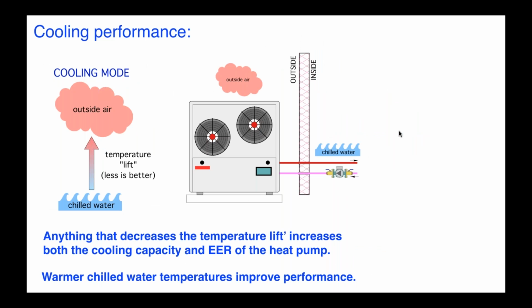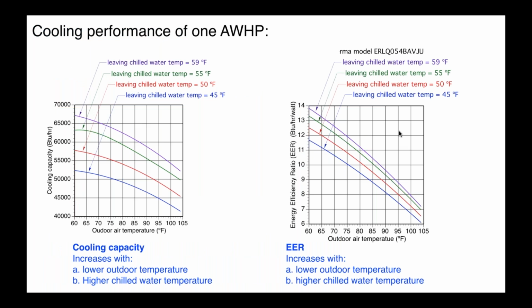Okay, cooling performance, real quick. The colder the water you're trying to produce, the less efficient the heat pump and the lower its capacity. You have a set of curves like this. And again, if you download the PDF, if I go a little fast through here, you can look at these curves in more detail. But what you're going to see, again, the lower the chill water temperature, the lower the performance of the heat pump, and vice versa.